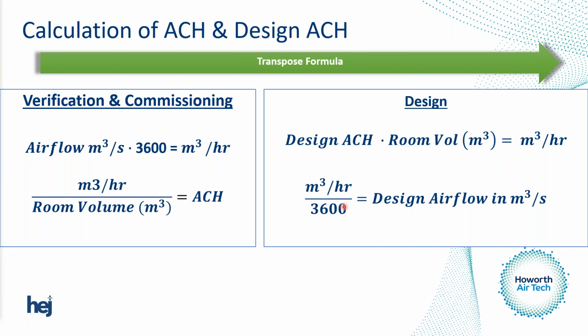Meters cubed per hour divided by 3,600 gives us the airflow. From there we can calculate if we can make a system work, calculate the ductwork sizing, and work out the runs through the Revit models, whatever it might be. But these are the formulas that we use.